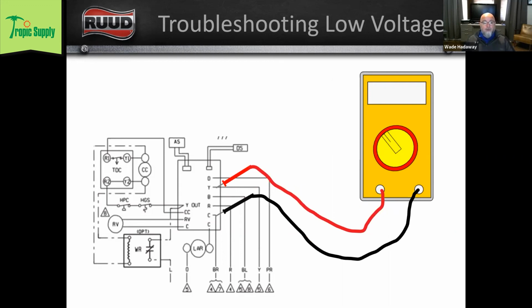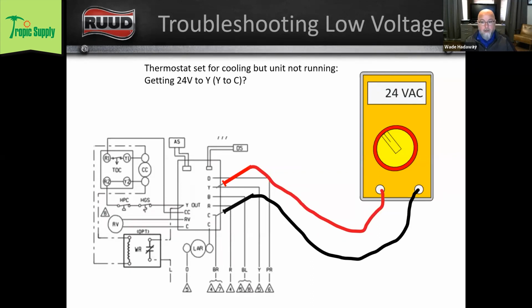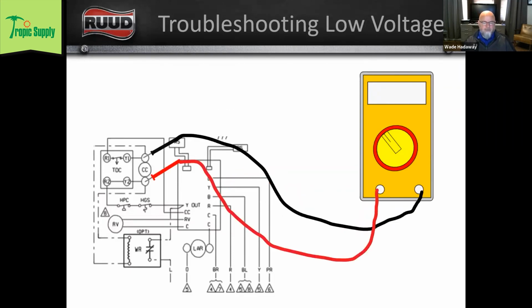So the next thing we're going to do is look and see, do we have a call for cooling from our indoor unit? So we have 24 volts to Y. Yeah, we do. So we're getting a call for cooling. So why is the unit not running?